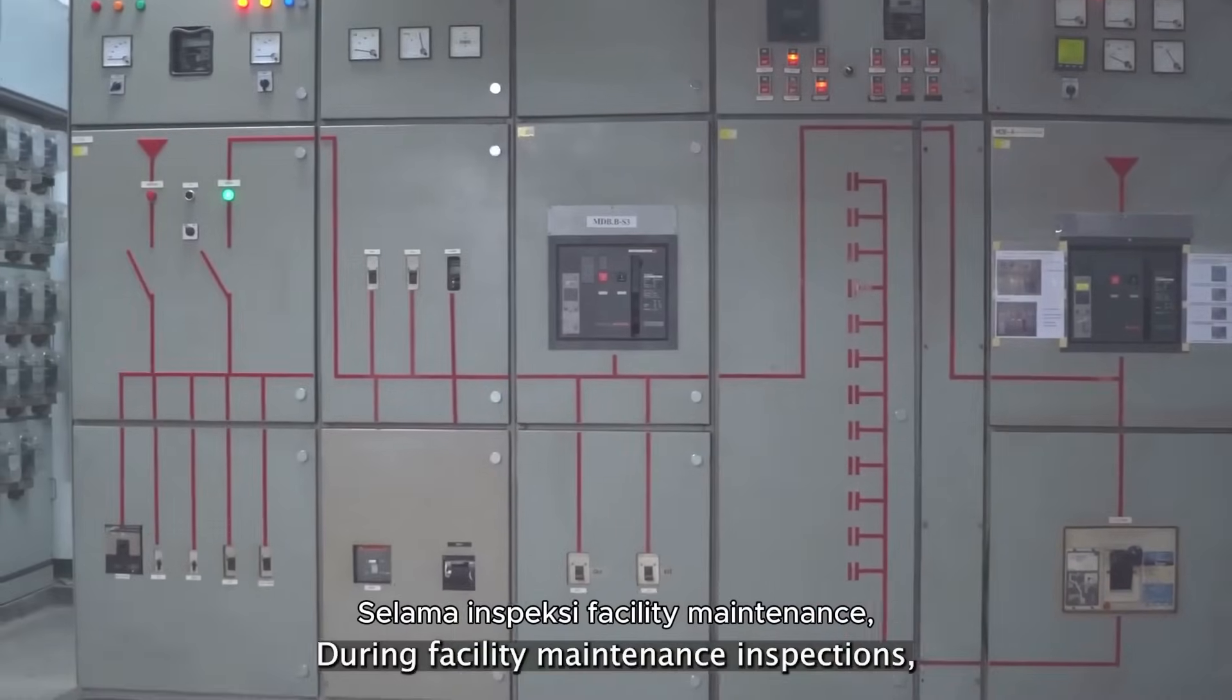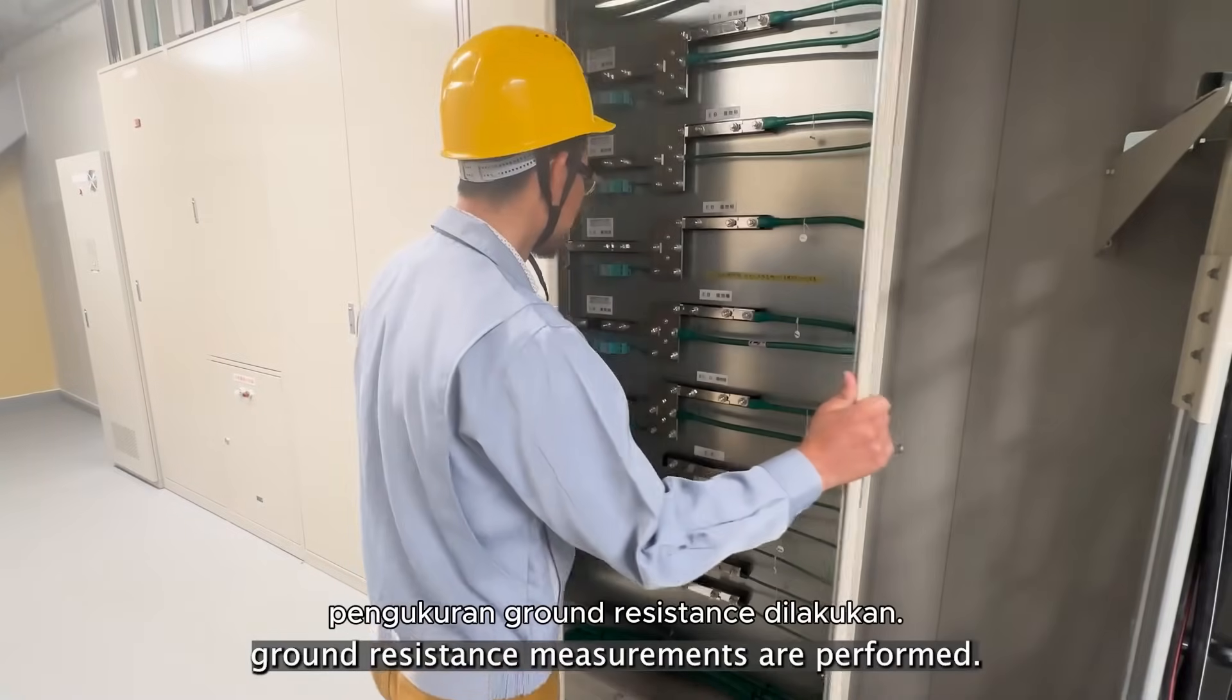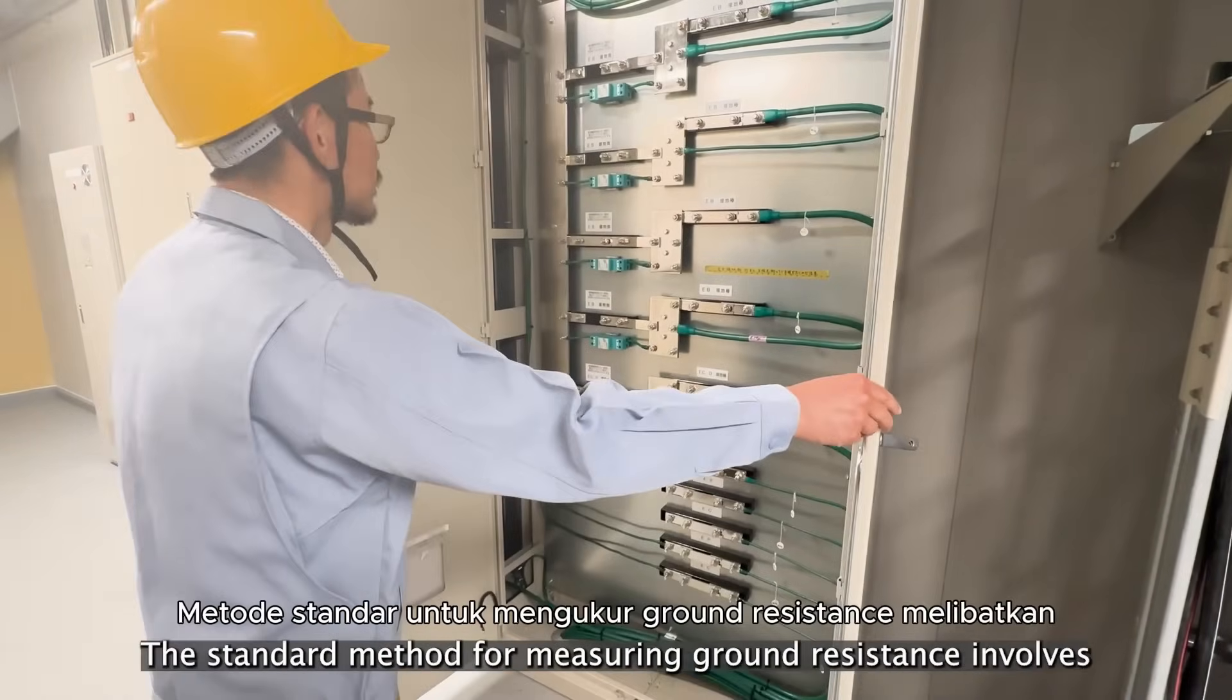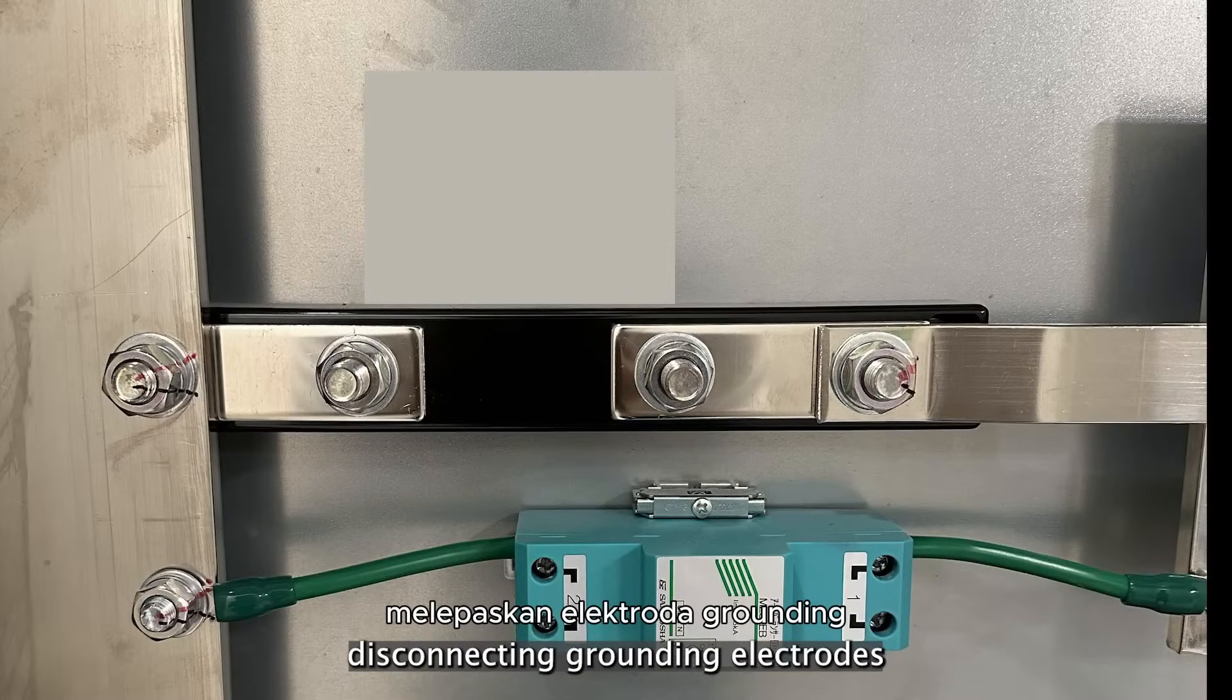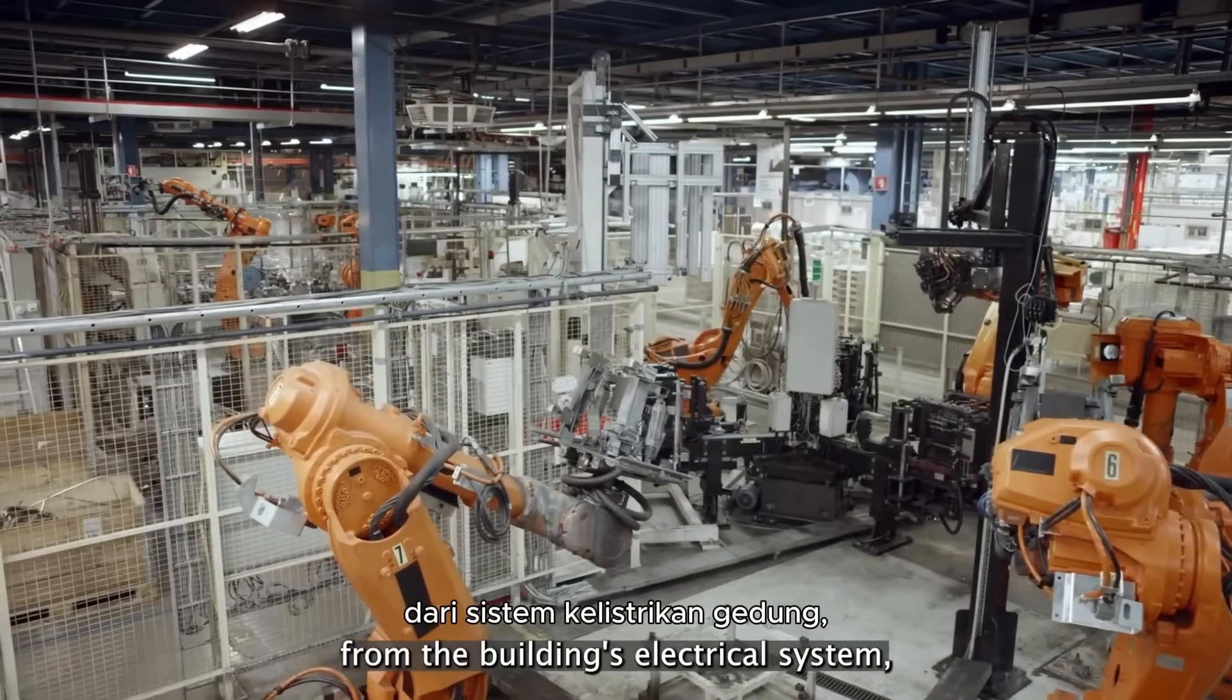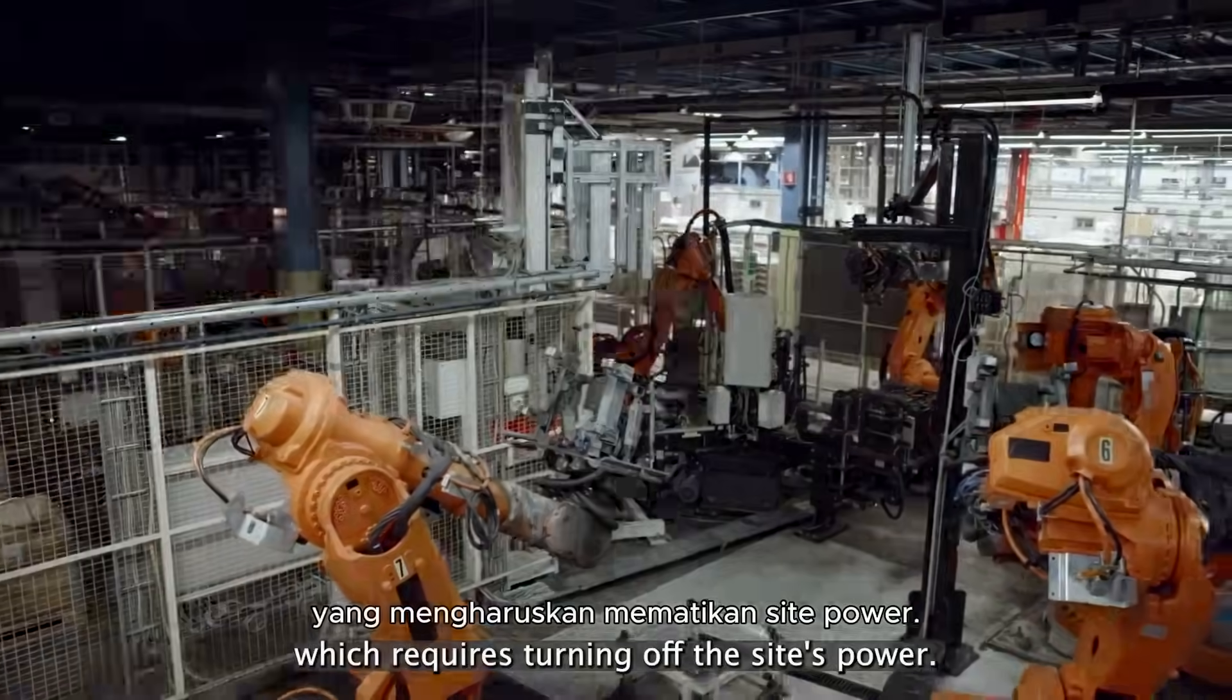During facility maintenance inspections, ground resistance measurements are performed. The standard method for measuring ground resistance involves disconnecting grounding electrodes from the building's electrical system, which requires turning off the site's power.